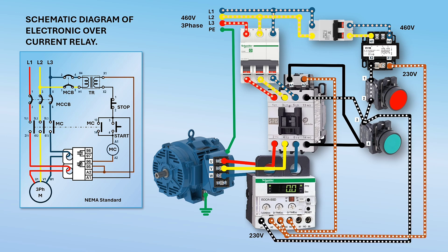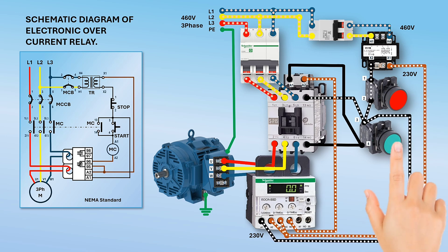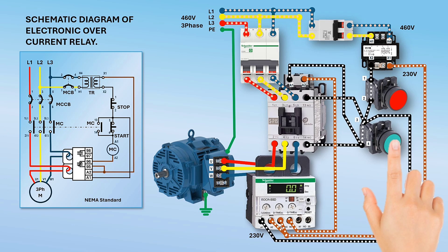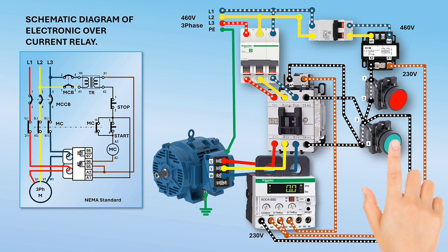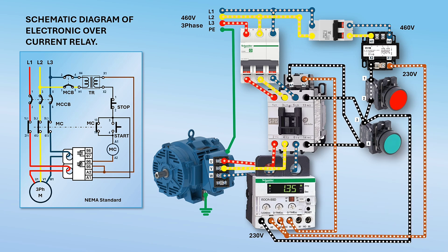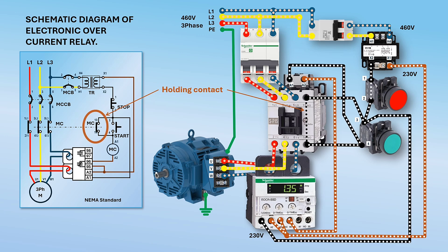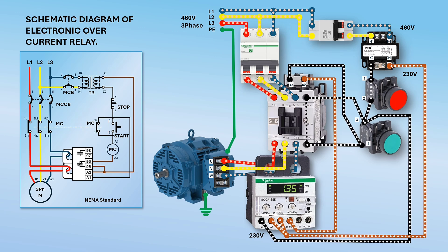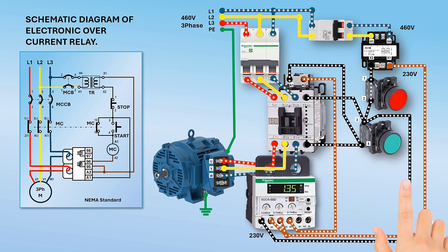At this condition, the motor is ready to start. Press the start button — the normally open contact of the push button will close and voltage will be available at contactor coil A1. Once the contactor is energized, all of its main contacts close, supplying voltage to the motor to make it run. At this instant, even if you release the start push button, the contactor will remain energized due to the closed position of the holding contact from the contactor.